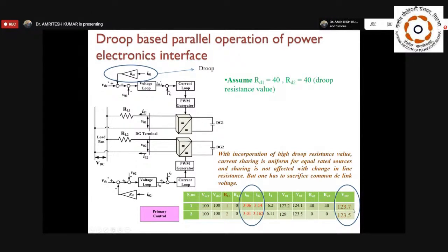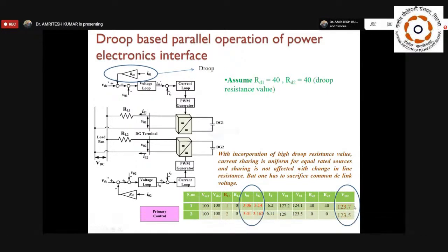Start with the very basics. I told you that initially the boost converter, with the common single DC link, will try to maintain a voltage of 250 volt. Now if we apply the droop control to get uniform power sharing, we come to a DC link that is very low, 123.7. So we are sacrificing the common DC link voltage. If the objective is uniform current sharing, then you have to sacrifice the DC link voltage. That is the major disadvantage of the primary control that people used with the droop control, and generally without communication people used to work with the droop control. They are able to achieve very good current sharing, but they have to sacrifice the voltages.